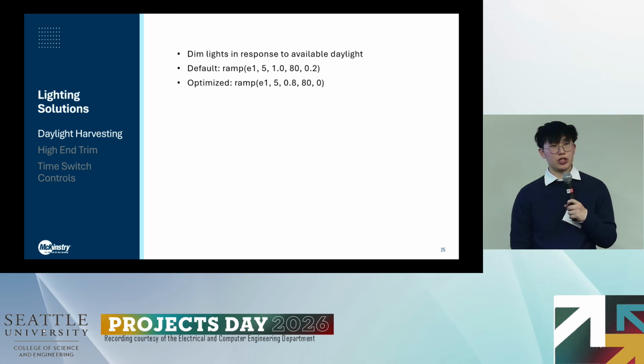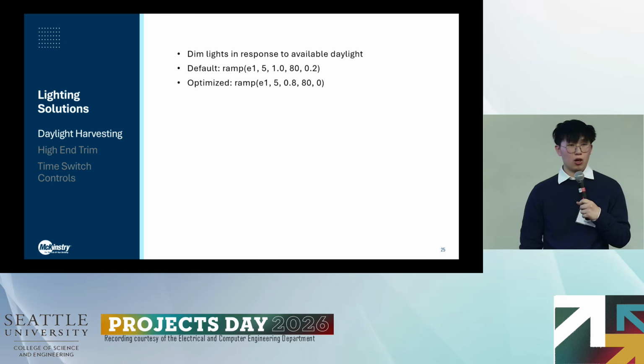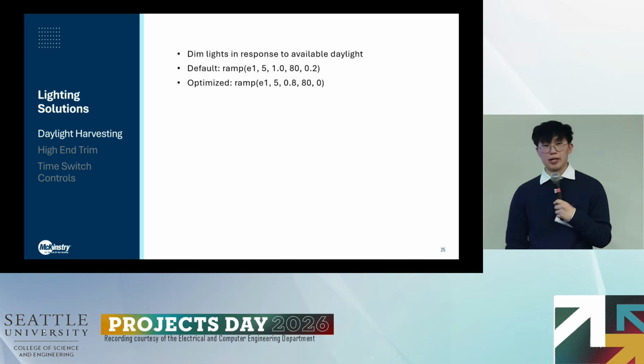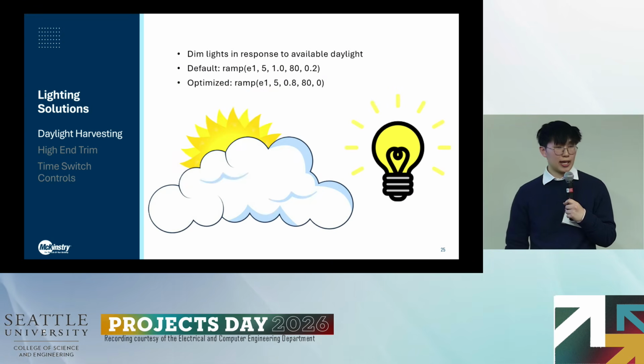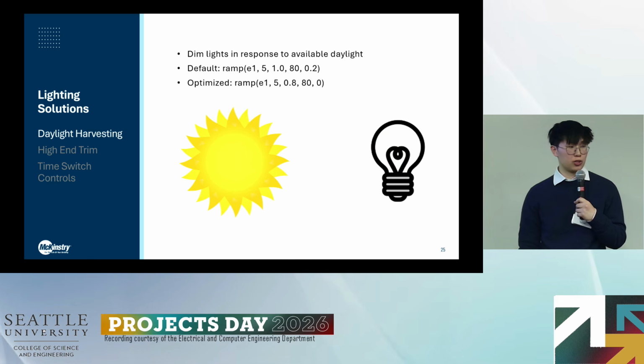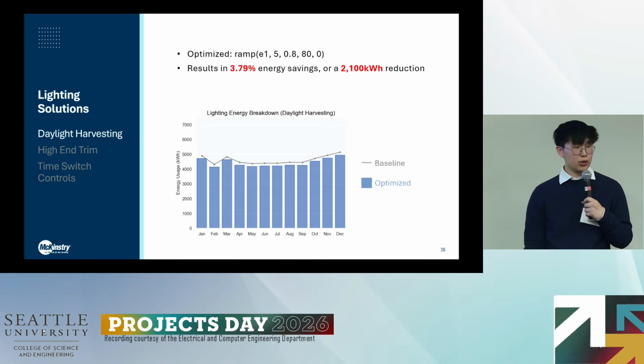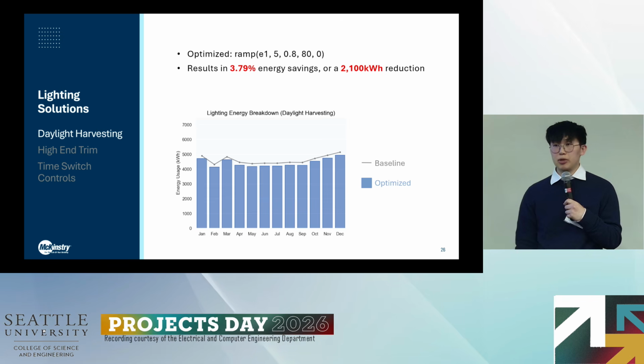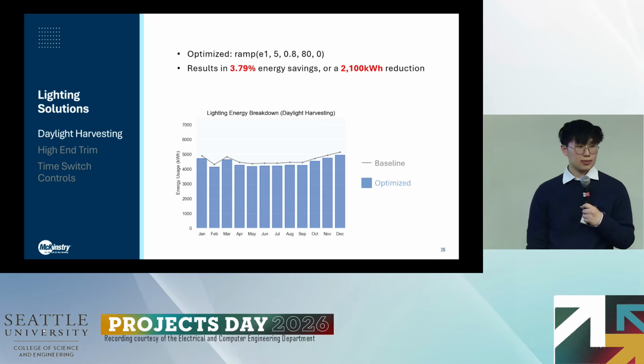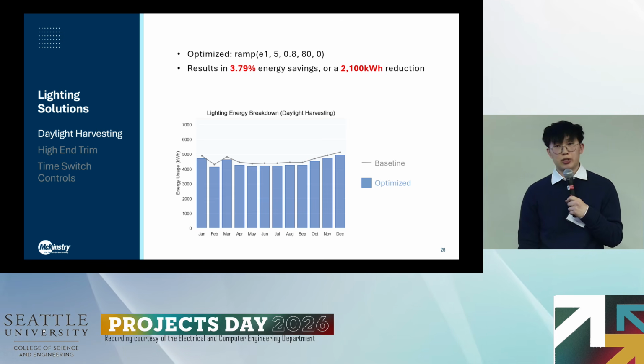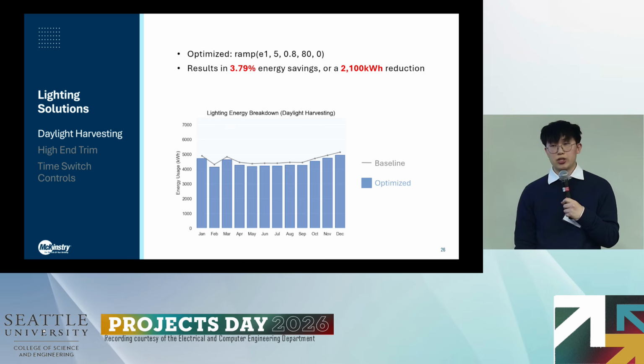So our first optimization is daylight harvesting, which dims artificial lighting in response to available daylight. We are given a default ramp function in IESVE, and we optimize this ramp function so that at 5-foot candles or less, the lights go up to 80%, and at 80-foot candles or more, the lights turn off. And using the optimized ramp function, we get the monthly total shown in the graph there. And this results in about 3.8% in energy savings, or a 2,100 kilowatt hour reduction from the lighting baseline.